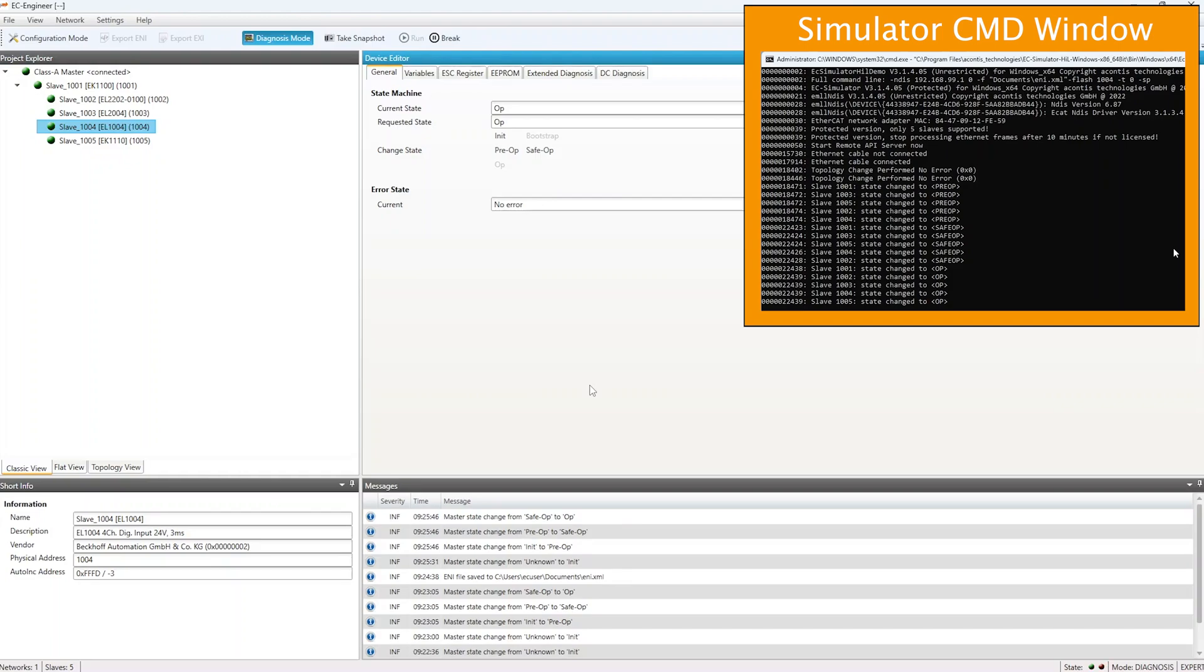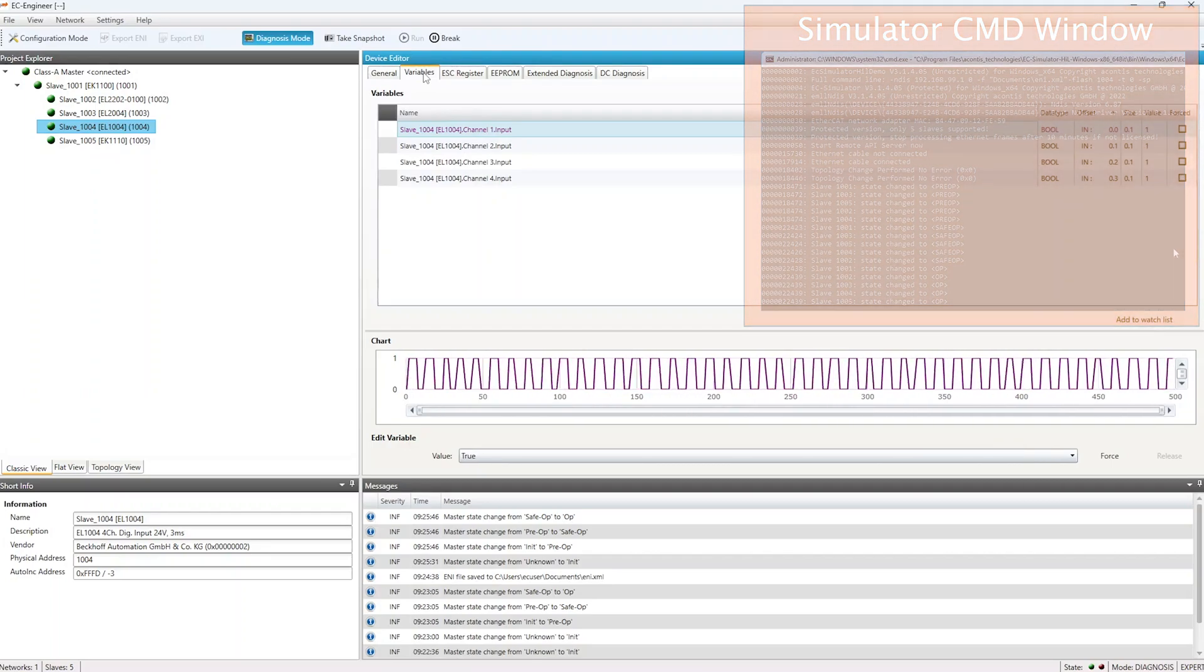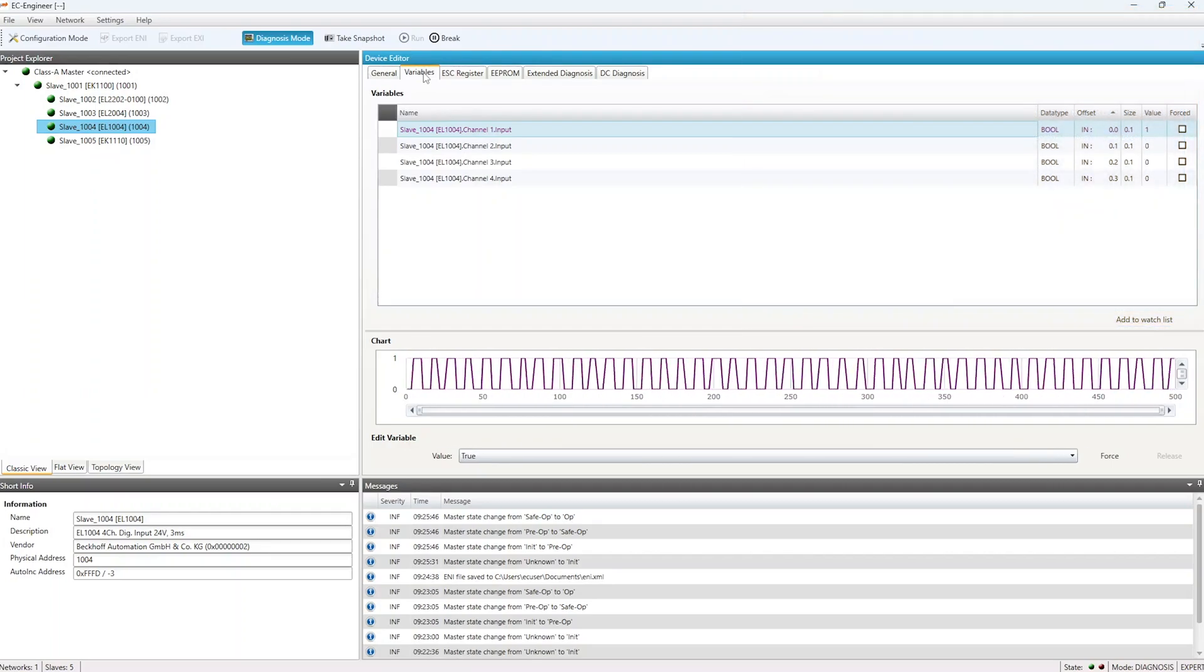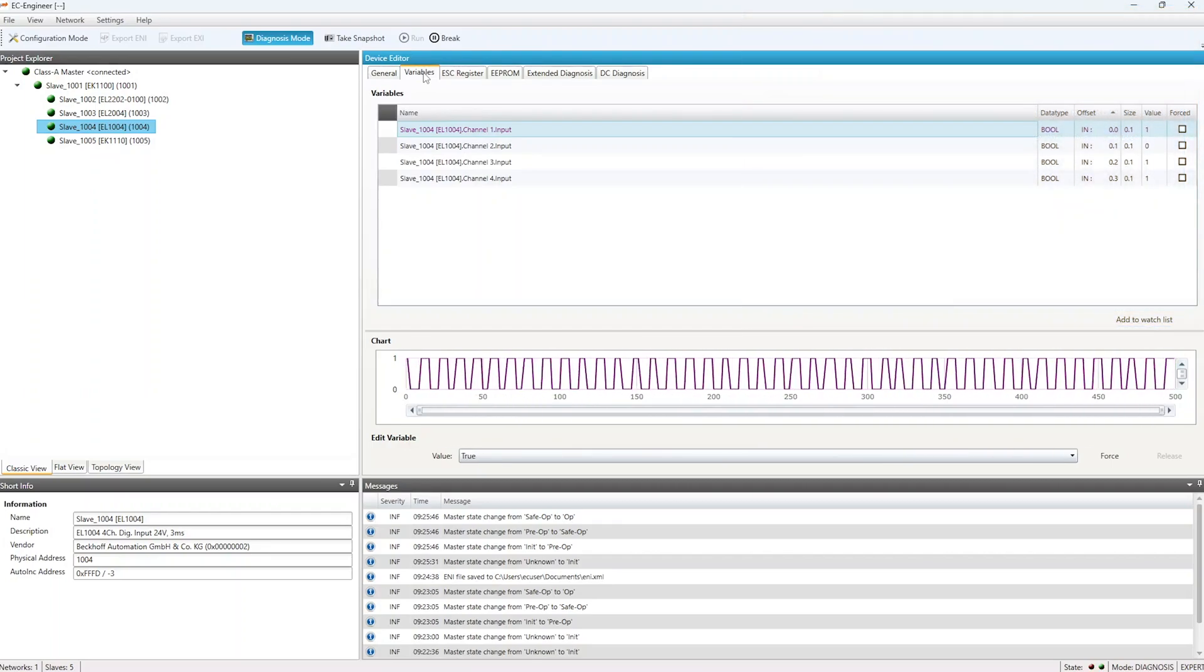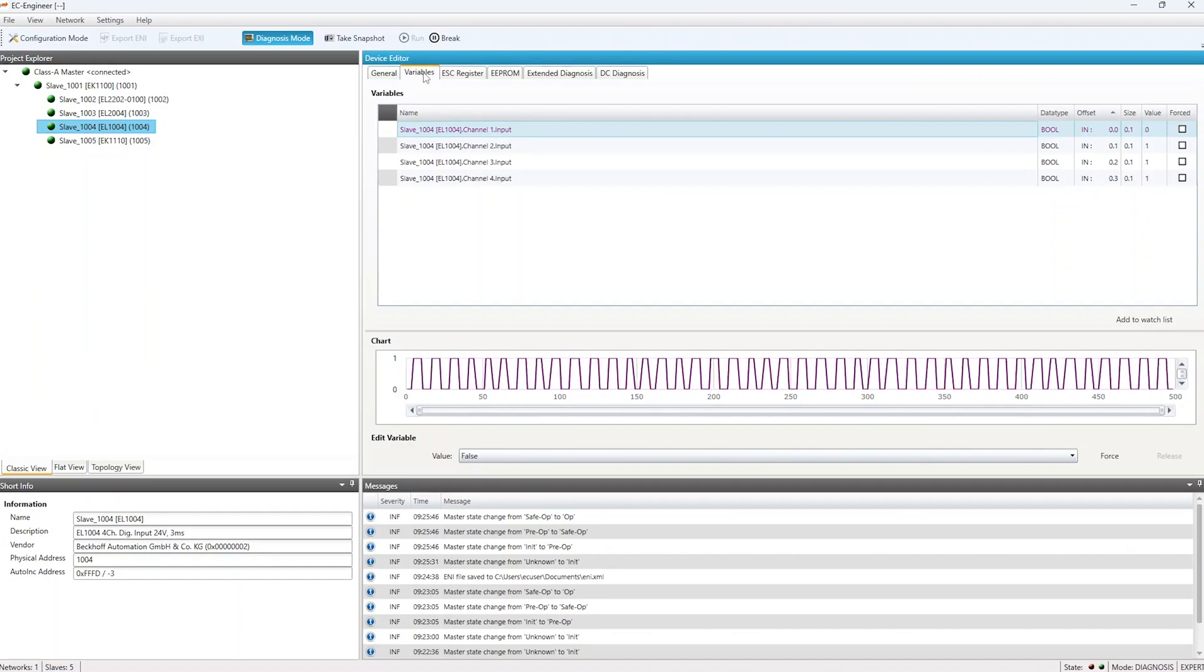We can further use EC Engineer to check the digital outputs that the simulator is flashing on the slave with station address 1004. Click the Variables tab when slave 1004 is selected, and you can see the digital output values changing in the chart area.